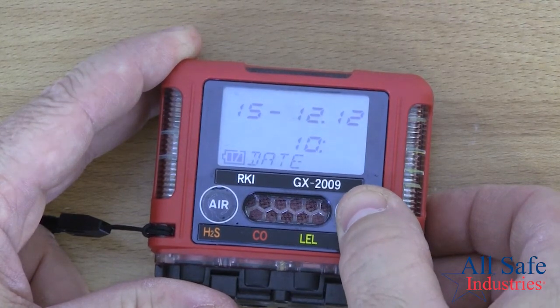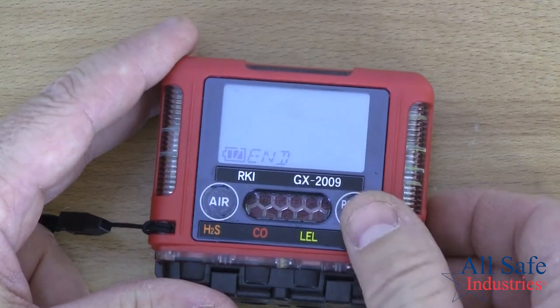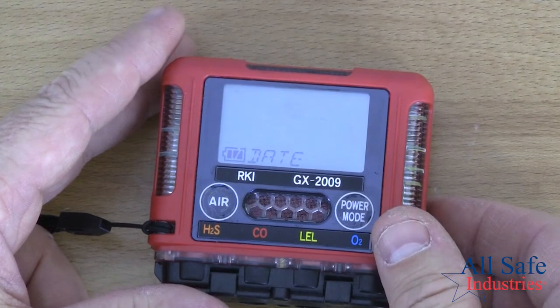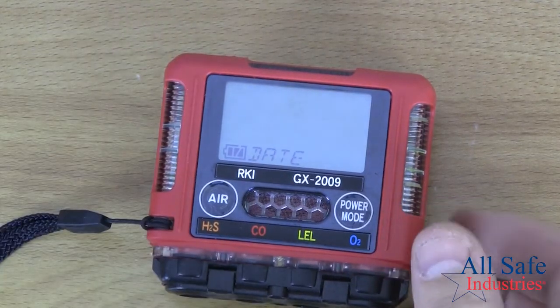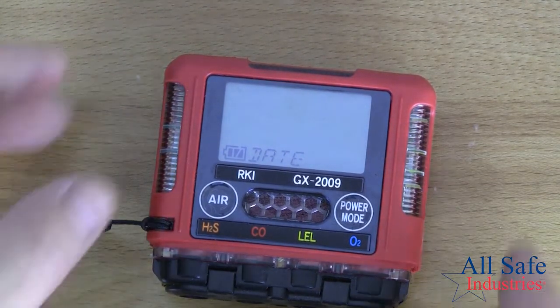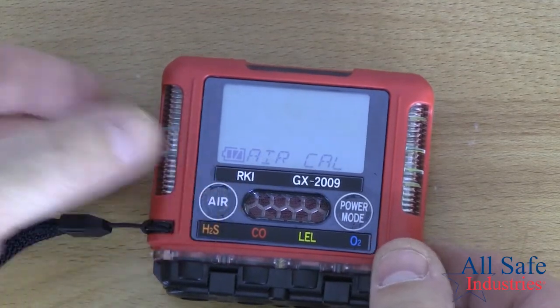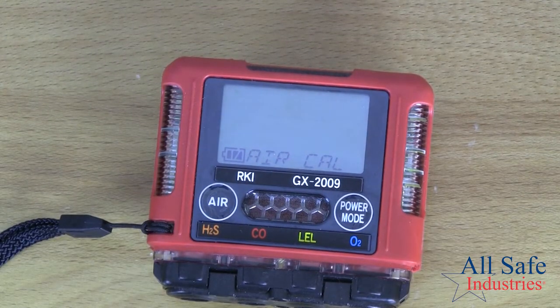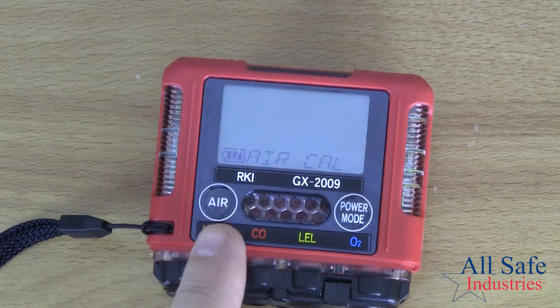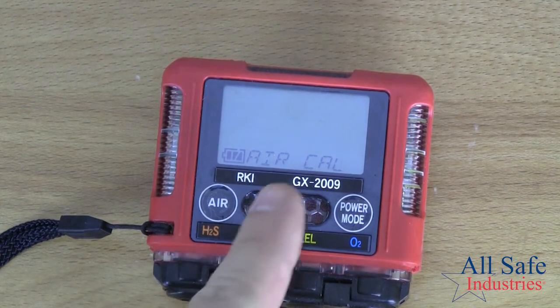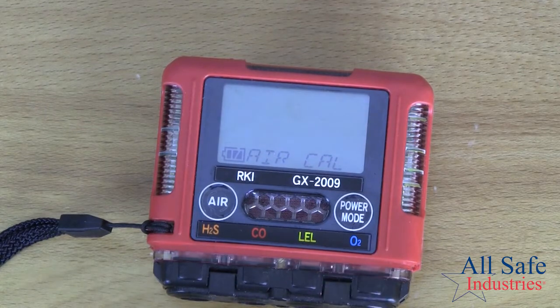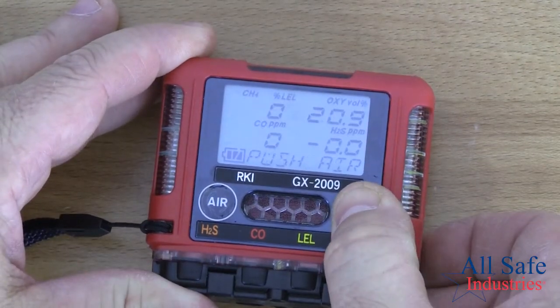I'm pretty happy with the time and date the way it is, so I'm just going to tab through all of those, and then I'm back to the date menu. If I don't want to change the date, I'll press the air button, and that brings me to the air cal screen, which is the fresh air calibration like we did before. So again, if I use my air button to scroll to the next menu item, and then I want to select that, I press the power mode button.